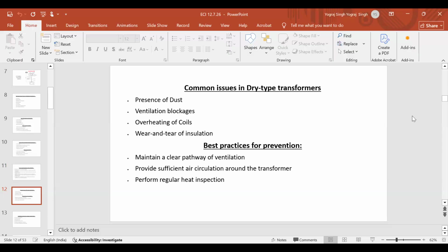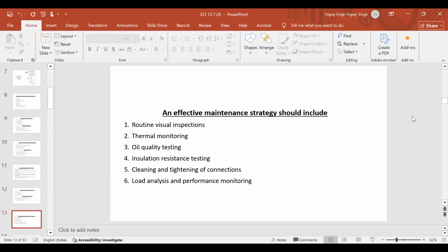Next, what should be the best way to prevent this? Maintain a clear pathway, provide sufficient air circulation, and perform regular heat inspection. Generally the transformer is a forgotten entity. If not every day, then every week or 15 days, all these parameters should be checked, noted and recorded so that when you take the next reading, you have something to compare. So, in case of power system maintenance, recording of parameters is very important.